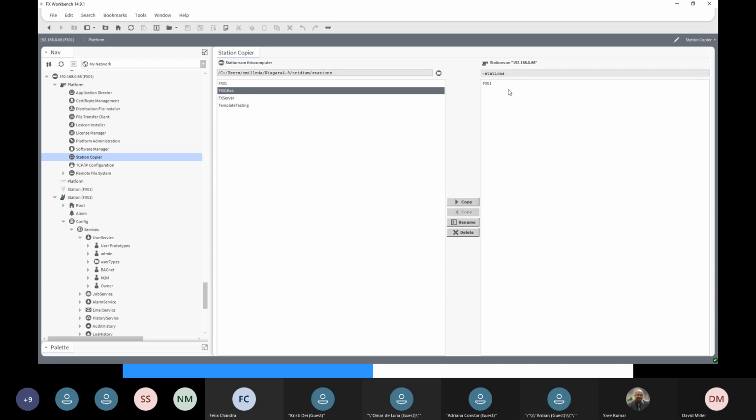You're now faced with restoring the platform, and you do that by, there's a backup and restore button on the FX80. You hold that button down while you turn the power off. You power up the FX80 with that button pushed, and you've got to be connected with a serial terminal.